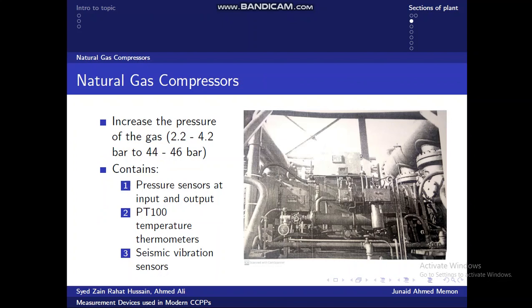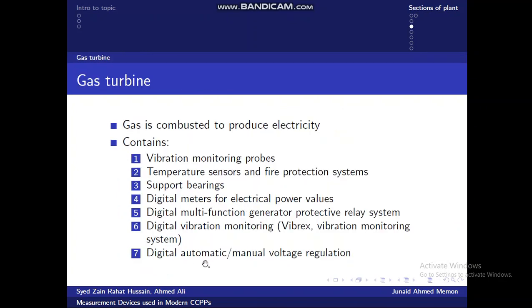So the next part is the natural gas compressor, where the gas is compressed before it is passed through the gas turbine. This also helps improve flow. So the pressure changes from between 2.2 and 4.2 bar to between 44 and 46 bar, where 1 bar is 100,000 Pascal, so that's a big change in the pressure. So over here we also have pressure sensors that are present at the input and output. We have a PT100, which is a platinum thermometer, and then we also have seismic vibration sensors.